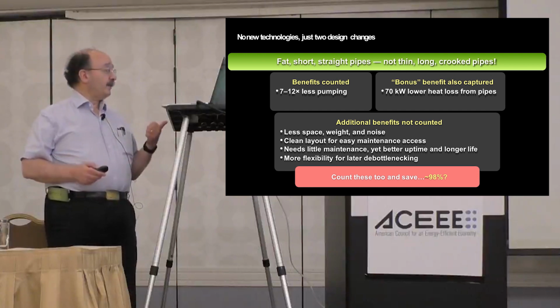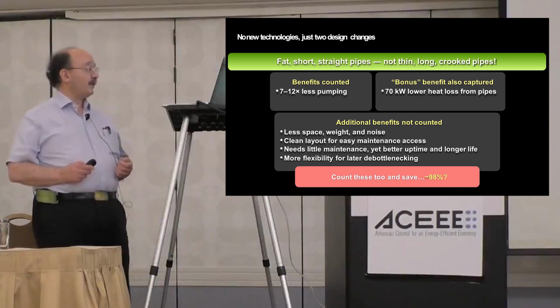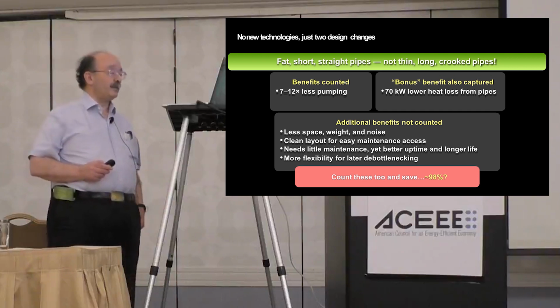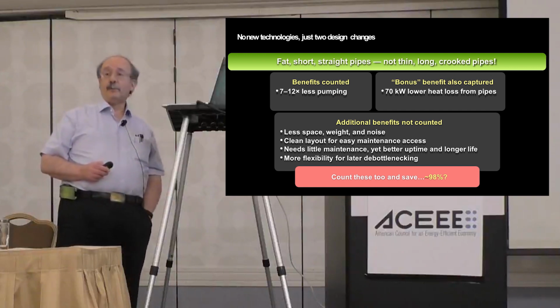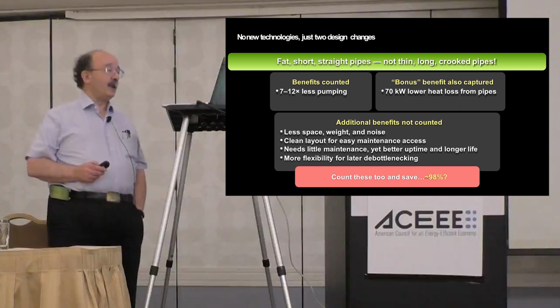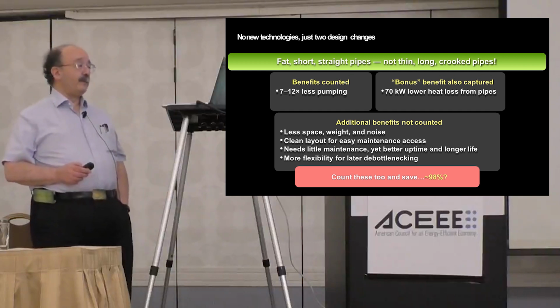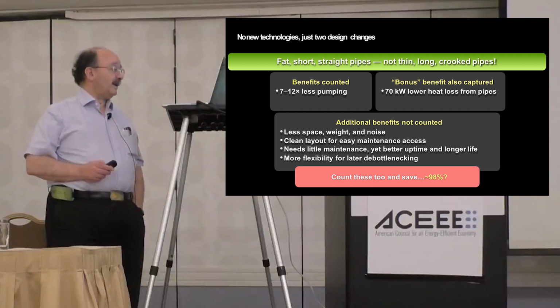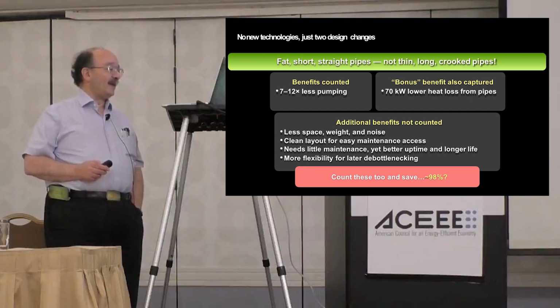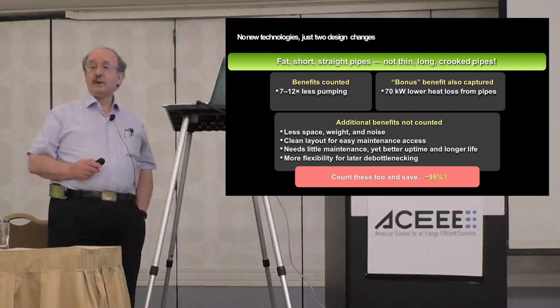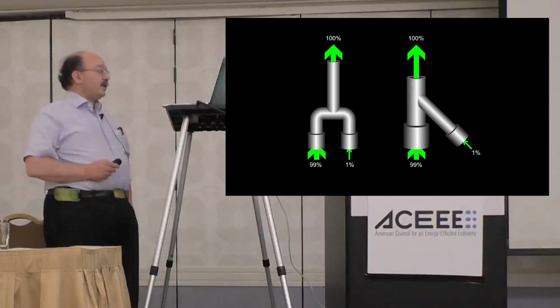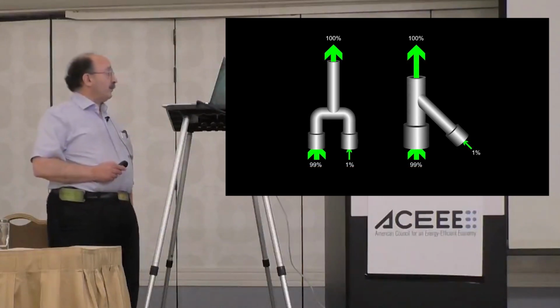I later estimated that if we had properly counted and valued those extra benefits, we would have saved not 86 to 92% of the pumping energy, but probably nearer 98%, and the capital cost would have been even lower. By the way, later we added some piping in my own house and saved about 97% of the friction and pumping power.